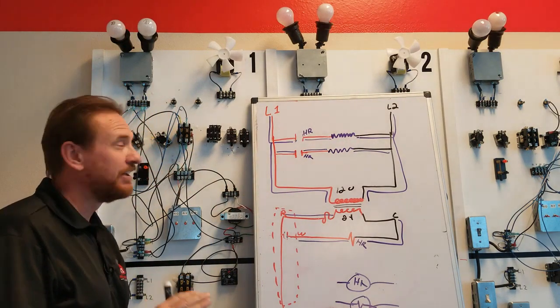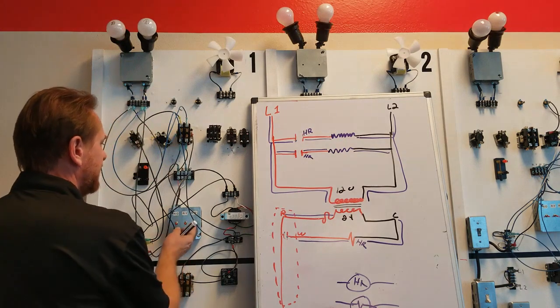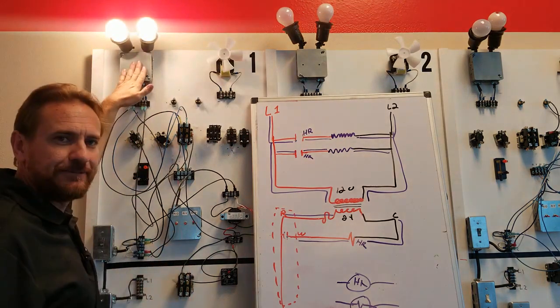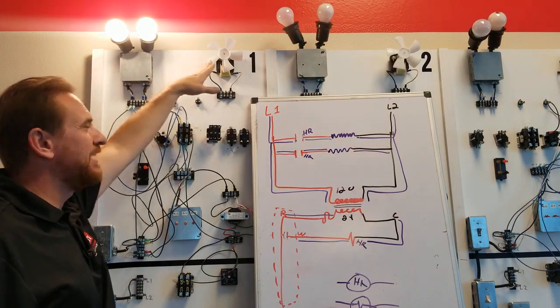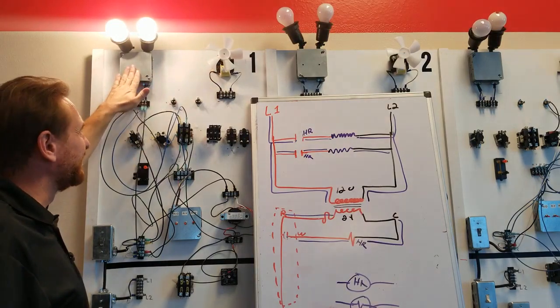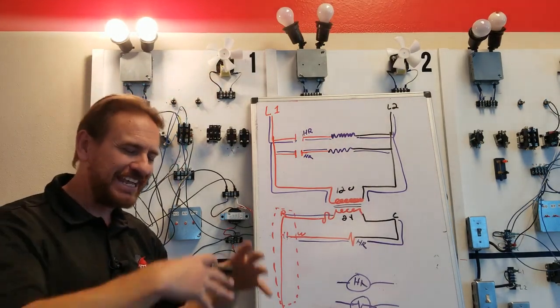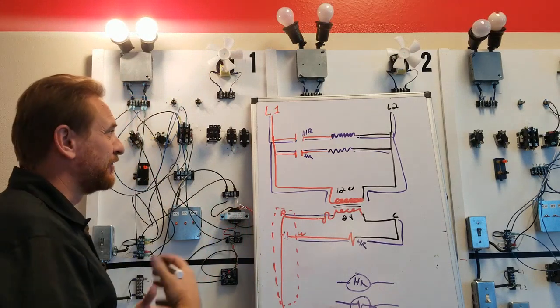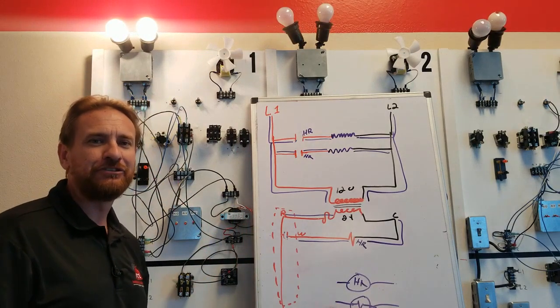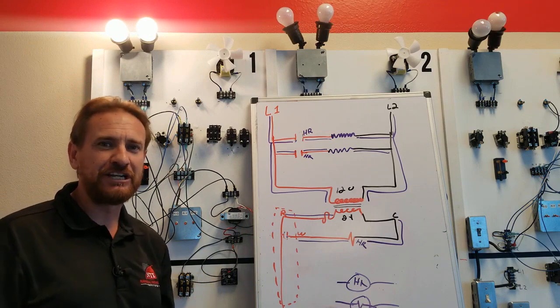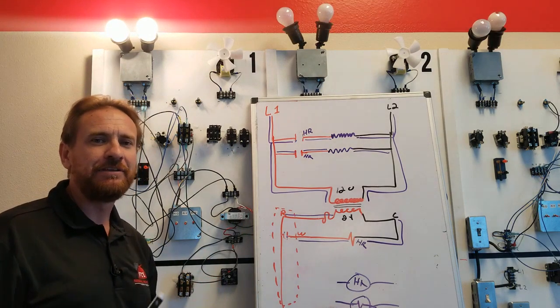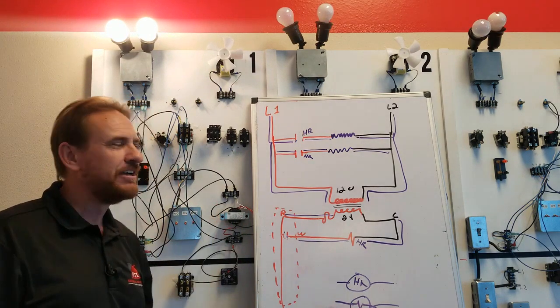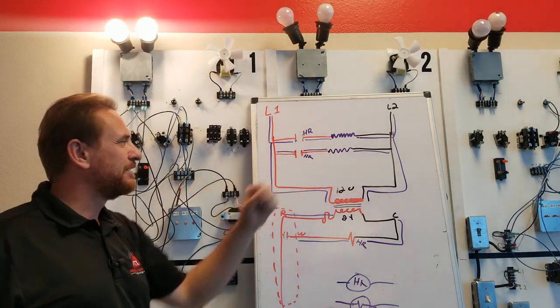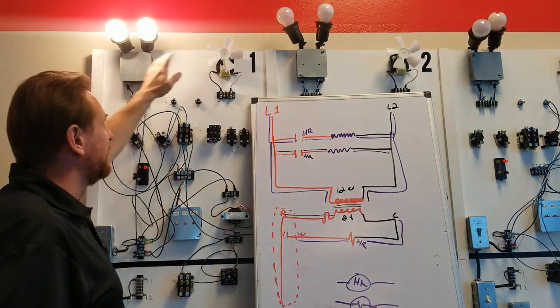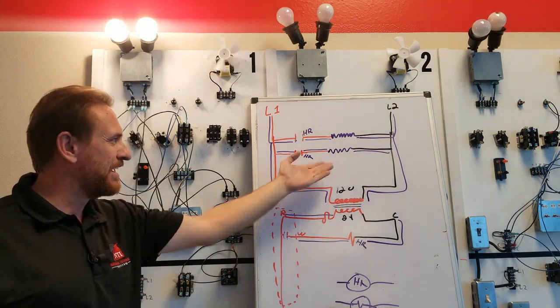If we have our heaters running, we need to make sure our fan's running as well. If the heater's running and the fan's not, all that heat builds up in the cabinet and trips a limit switch. Anytime a limit switch is tripping, whether it's gas furnace or electric, you need to be thinking airflow, airflow, airflow. I haven't drawn a limit switch in here, but we know the heaters are running and the fan's not on, and we don't have a fan wired in here.